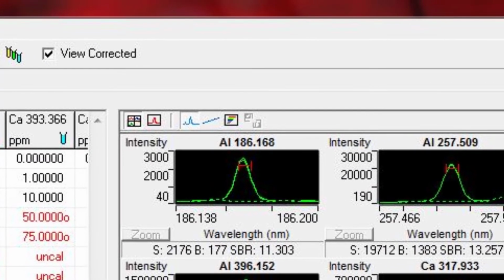Unfortunately, with wide ranges of standards, it's difficult to get a good linear fit across the entire region. Don't worry though, this is something we commonly deal with, and it's possible to tell the software if you are interested in the high or low end of the calibration run. Above the images on the right, click on the angled line button. This will show you the calibration points for each wavelength.